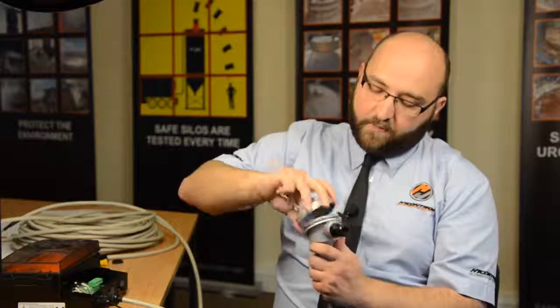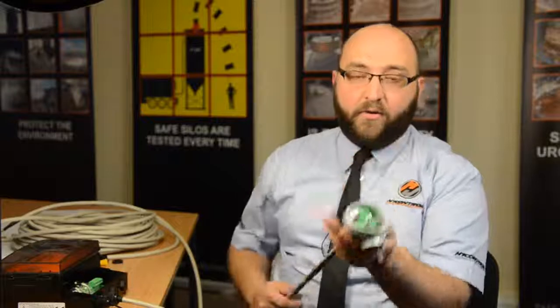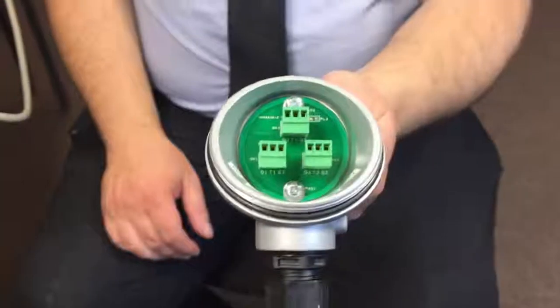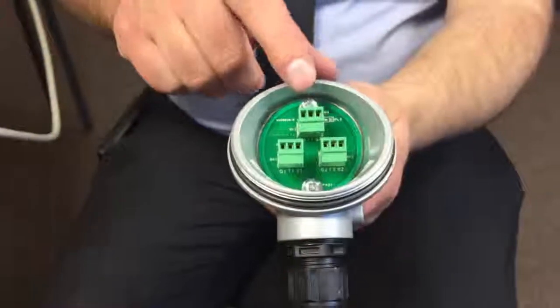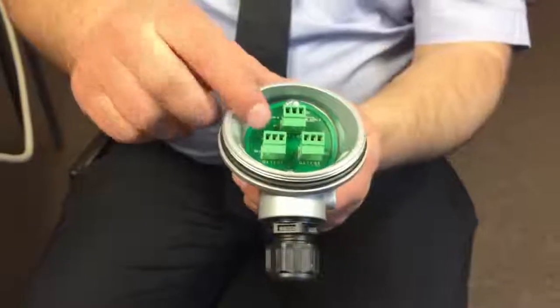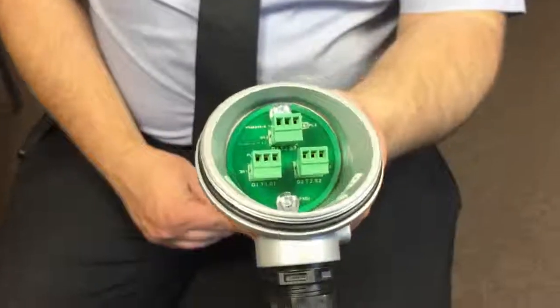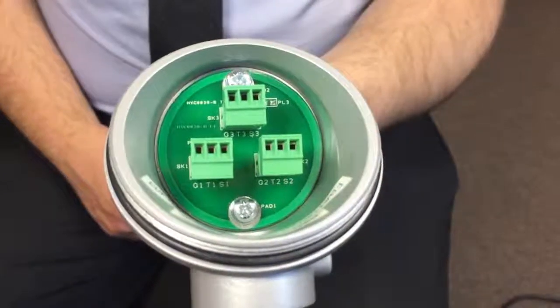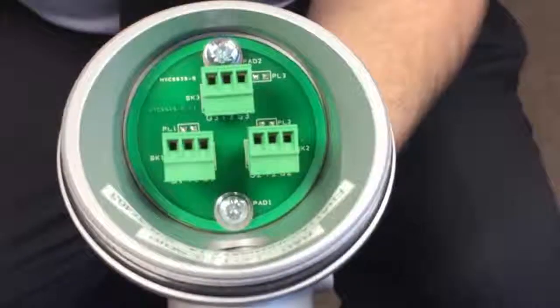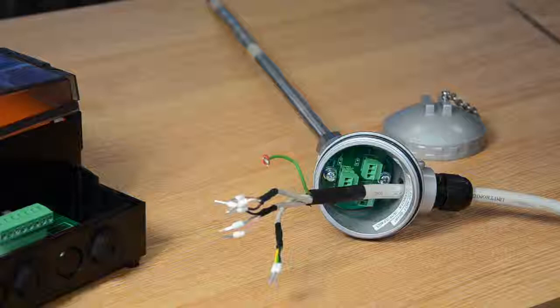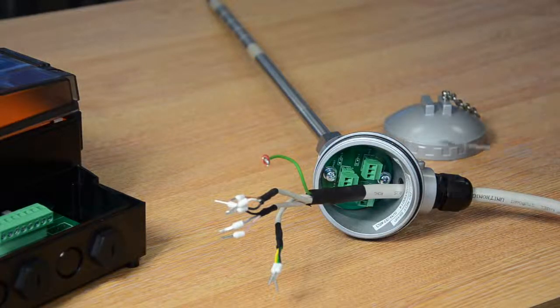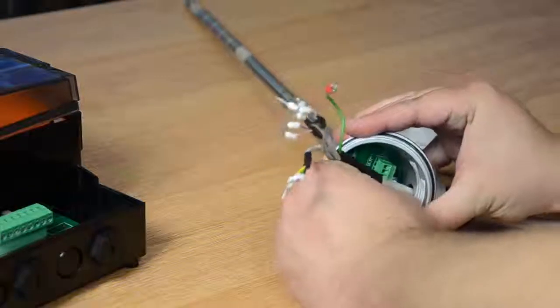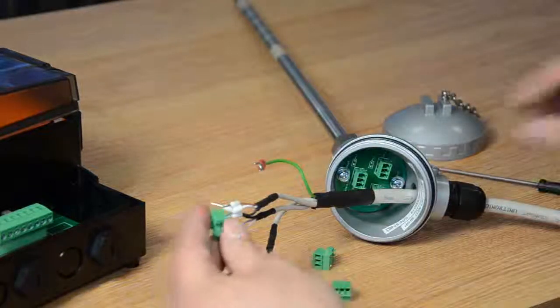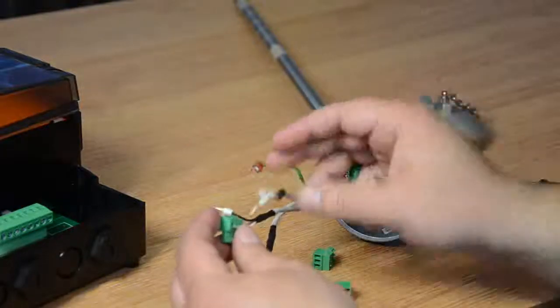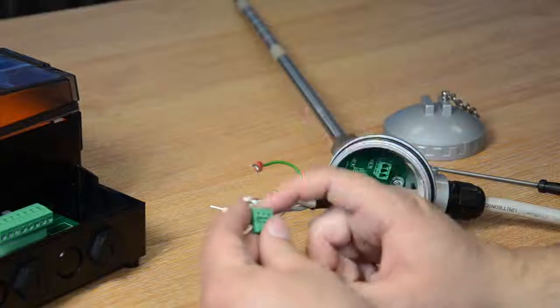When you open up the head of the probe, you'll be greeted with a circuit board that looks much like this. Once again, you'll have 3 separate terminal blocks, and they'll be marked up SK1, 2 and 3. Similar to in the controller, this is probe 1, probe 2 and probe 3. You'll also notice it marks out which wires go where with the G, T and S, meaning guard, test and screen. So once you've fed your cable through your cable gland, you're going to need to remove your terminal blocks 1, 2 and 3. And much like in the controller, in the probe you're going to need the black cables on the left hand side, your tests in the middle and your sense on the outside.